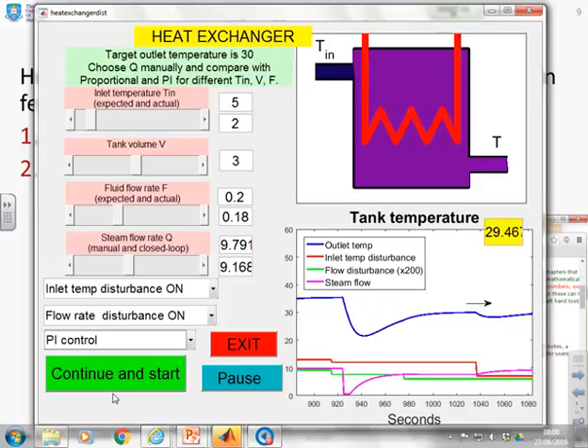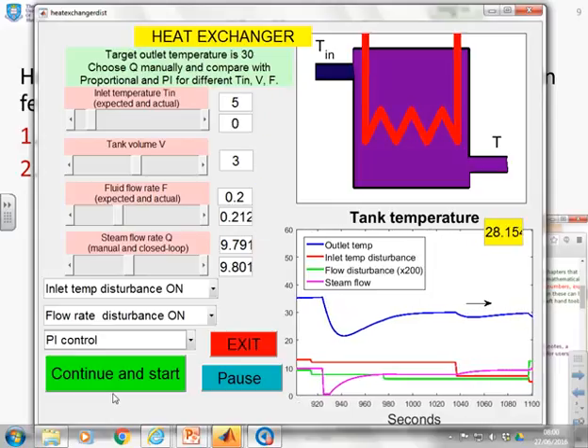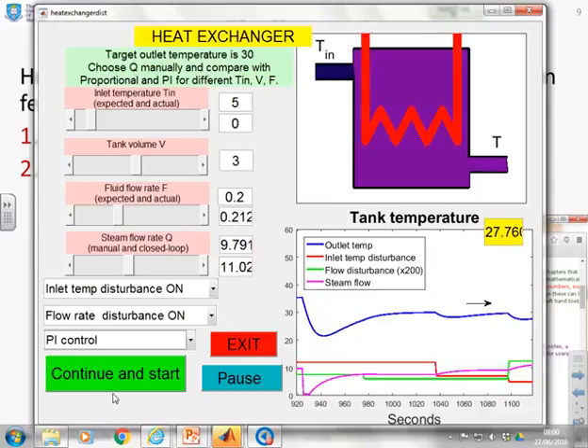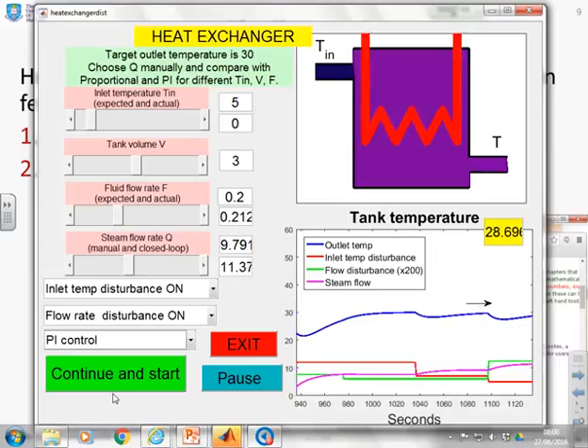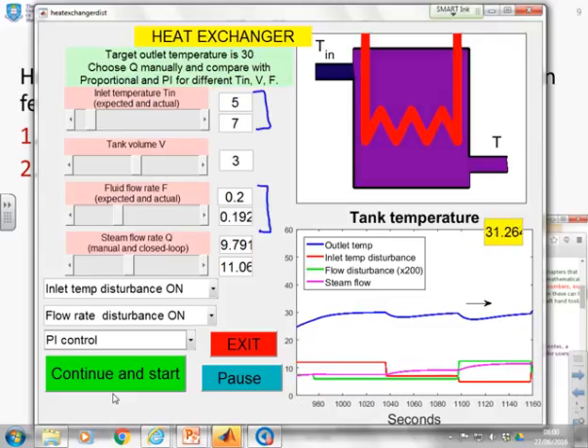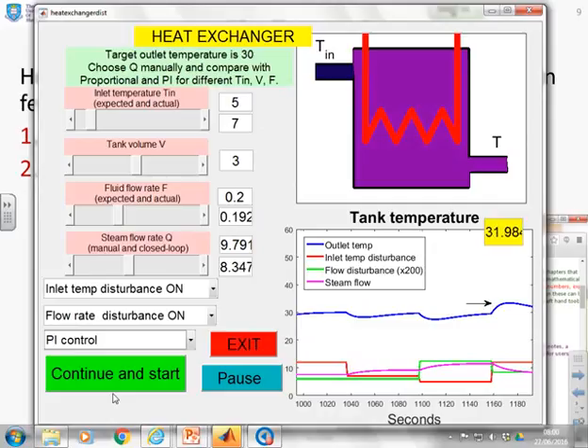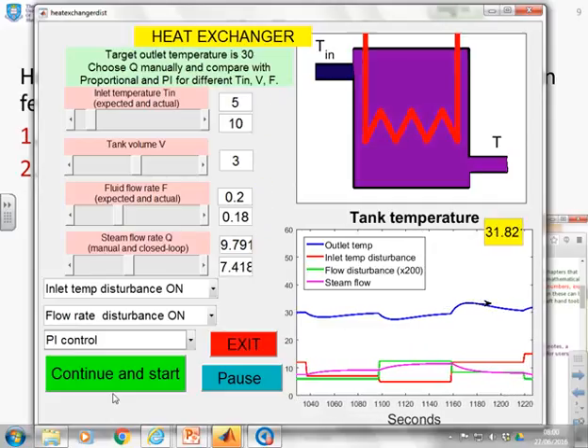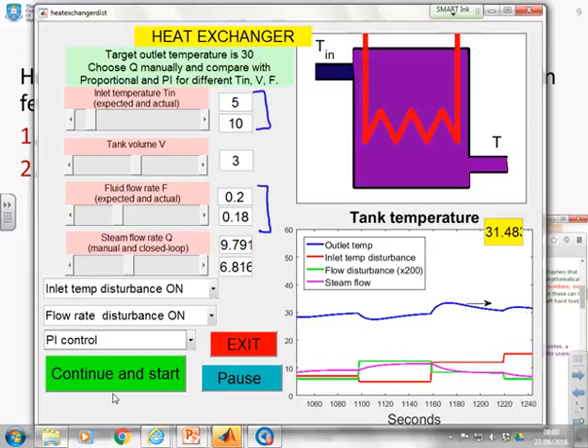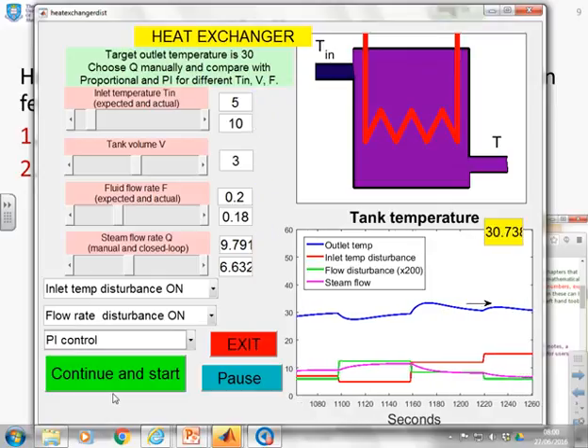And you'll notice that when the perturbations happen, when the inlet temperature and the flow change, obviously you'll get a transient bump. But the PI is bringing you back effectively and smoothly. And it's going to keep doing that all day. It's not going to get tired. Whereas if you had to do this manually you're going to struggle.